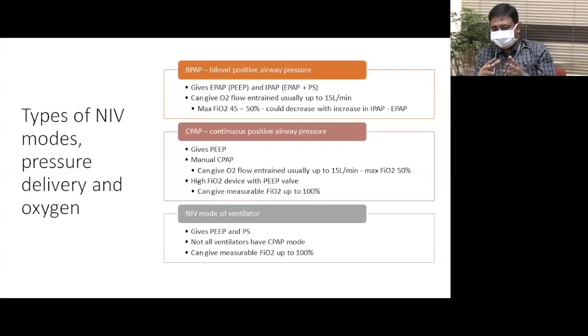The BiPAP is the conventional bilevel positive airway pressure machine. So this is not a ventilator. This is a standalone machine. It is able to give an EPAP, which is the same as PEEP in a ventilator, and the IPAP, which is a summation of the EPAP and the pressure support, if you talk in ventilator terms. And IPAP minus EPAP would be the pressure support.